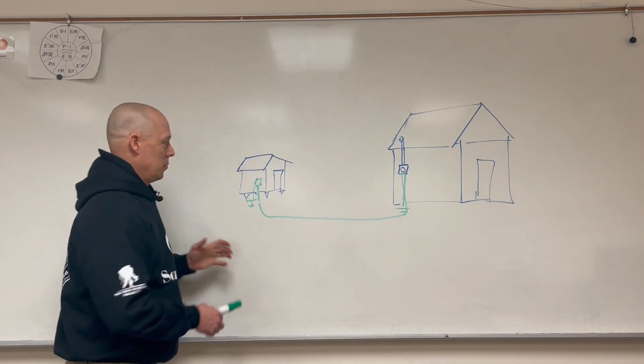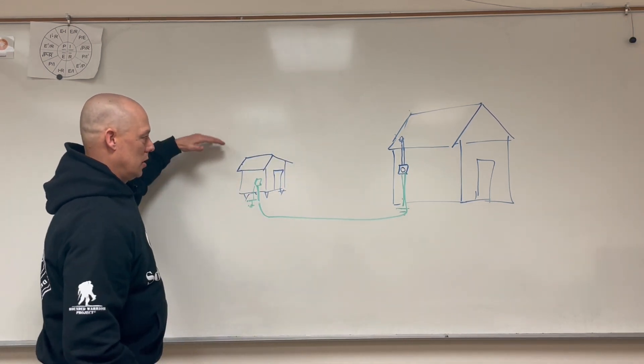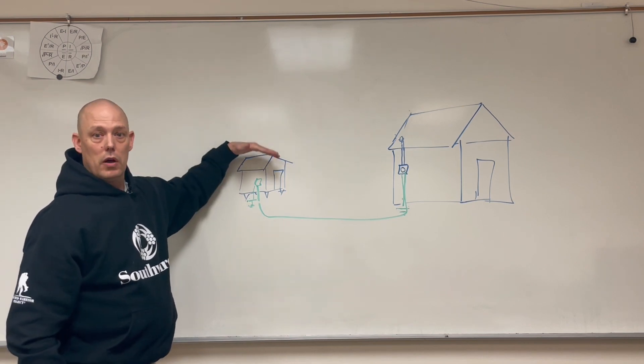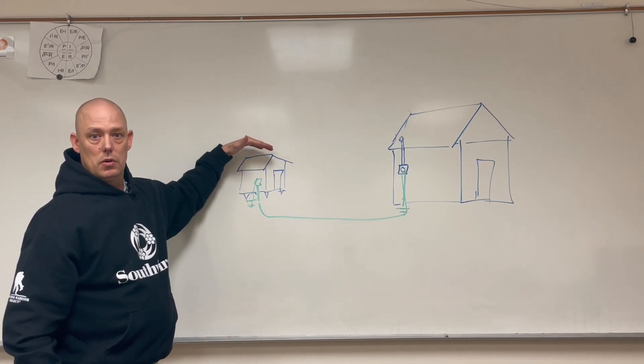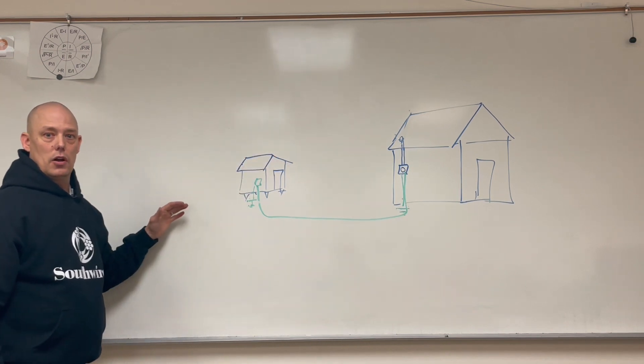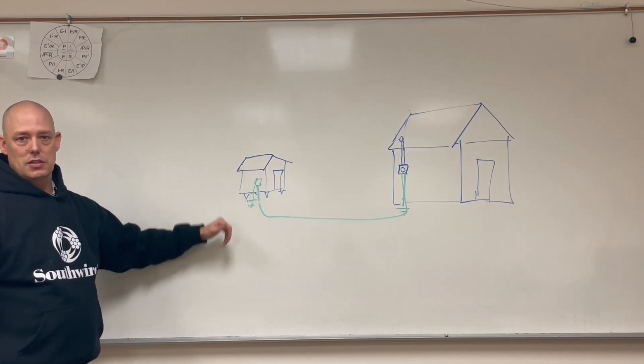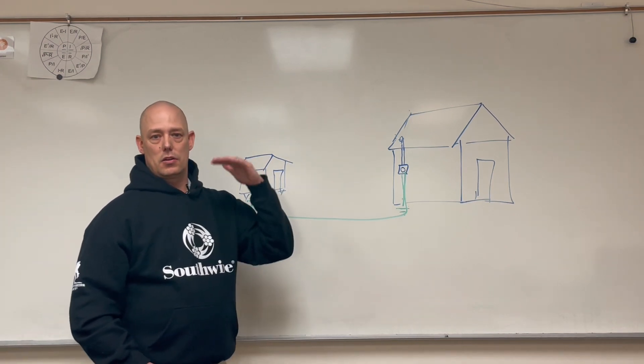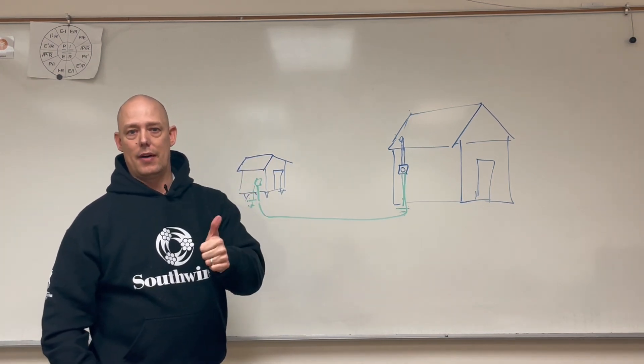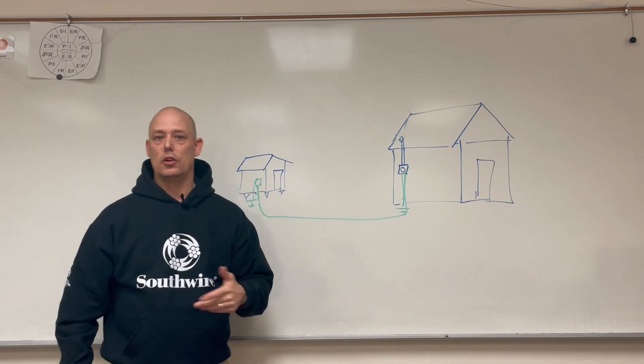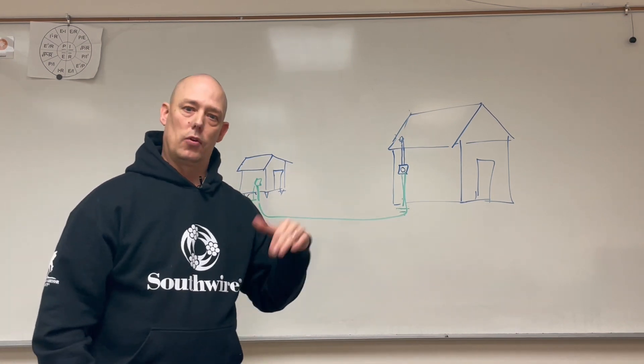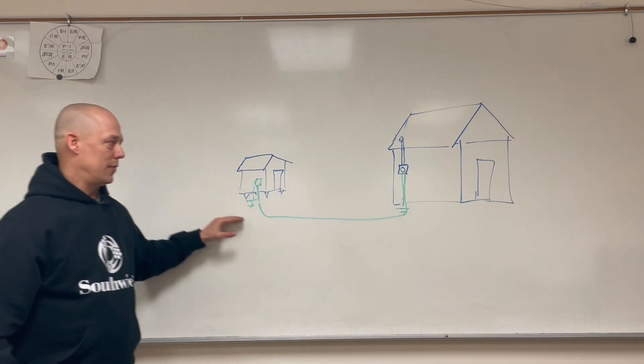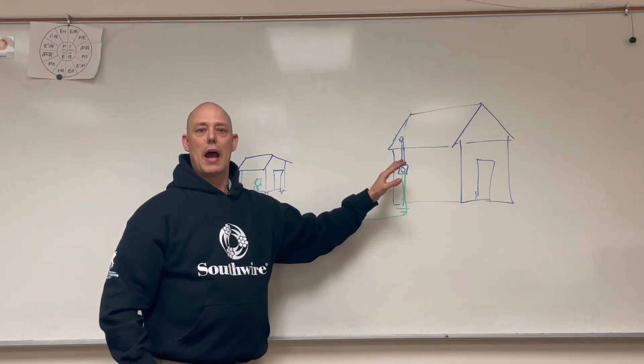We have to make sure we protect the shed, or another type of structure like a freestanding garage. That happens a lot — somebody has a freestanding garage with a lot of equipment, sometimes even a dwelling unit up top. You still have to put a panel in there; you can't just take one circuit. If it's a garage with automatic doors, you're going to need an outlet and lights — you'll have to have a subpanel. And if you have a subpanel, you're going to need to pound a ground rod or install an electrode, and you do have to have an equipment ground going back.